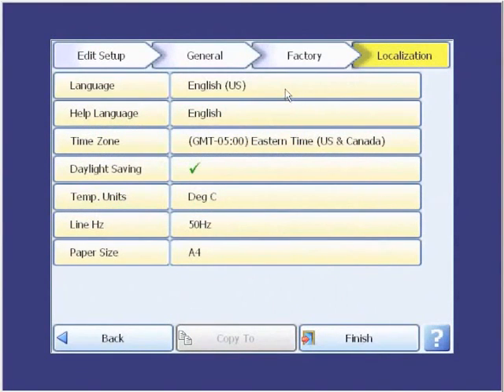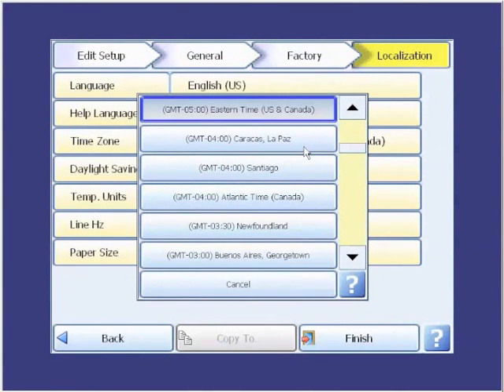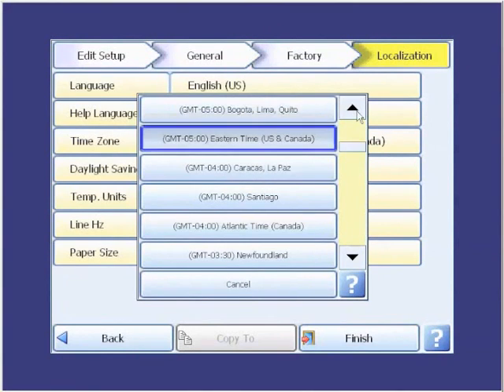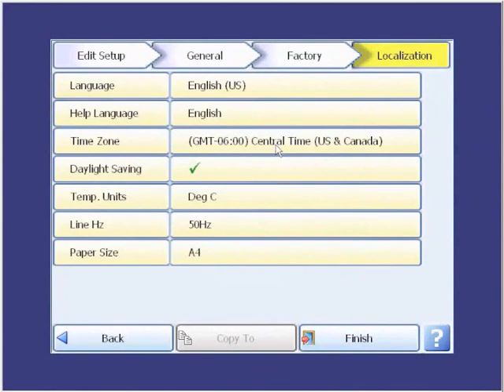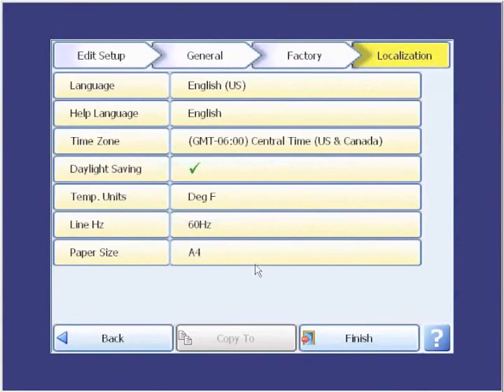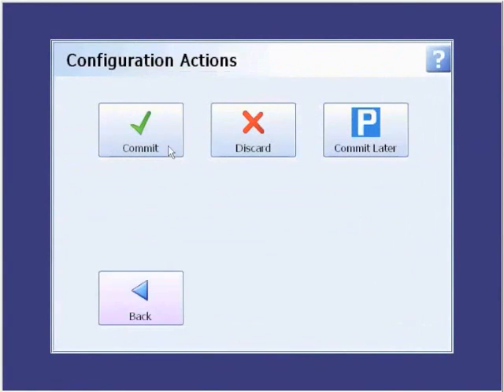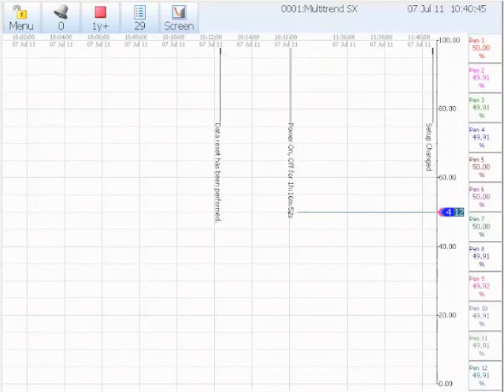We want to leave it at the English language and help at English. We want to change the time zone to central time. We click on that and get a pop-up screen, and we have to scroll up to get minus six for central time in the U.S. Click it and highlight it — it changes to central time. Daylight savings time is enabled. We want to change from degrees C to degrees F, and from 50 hertz on the AC line frequency to 60 hertz. Paper size only applies if you have a USB printer hooked up, so we can leave it. Then we finish and commit the changes. When it's finished, it comes back to the trend screen.